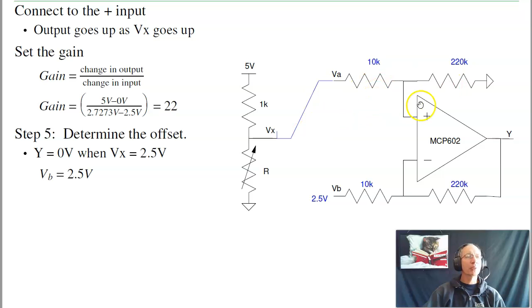As temperature goes 0 to 50, here's the resistance. From voltage division, that's the voltage at Vx, which is actually VA. The gain that I want is change in output over change in input. I want a gain of 22. The offset is the lower end. That's just special for this case. That's not always true. And the output is gain times A minus B. So if I plot that, sure enough, it's going from 0 volts to 5 volts as temperature goes 0 to 50 C.